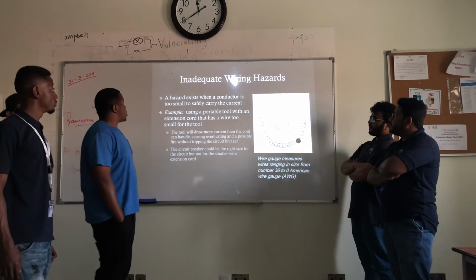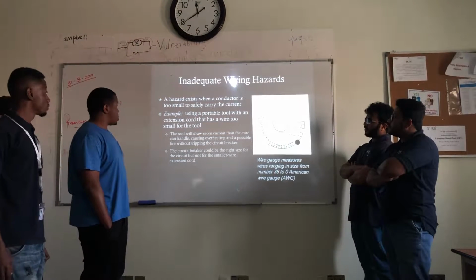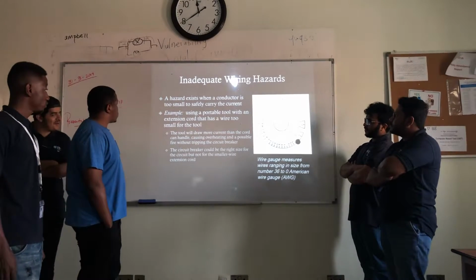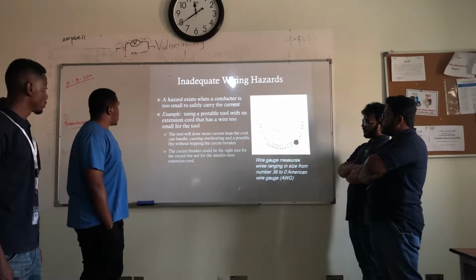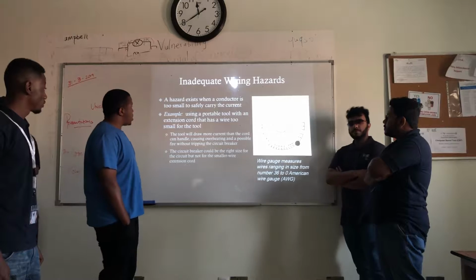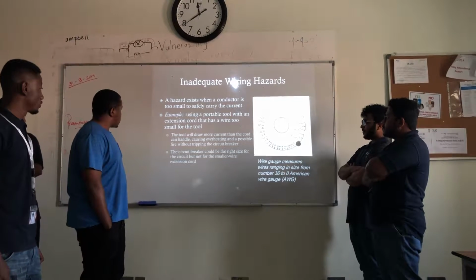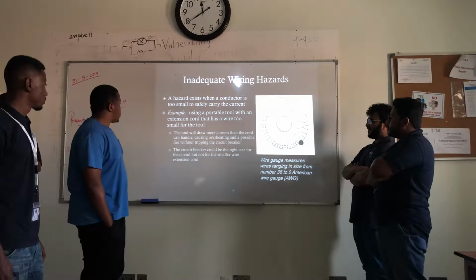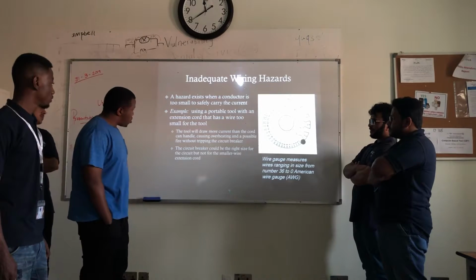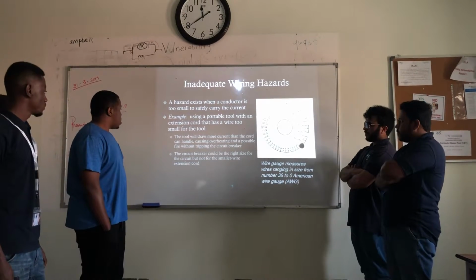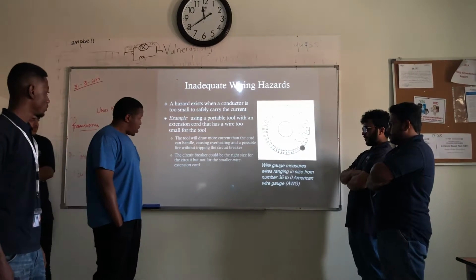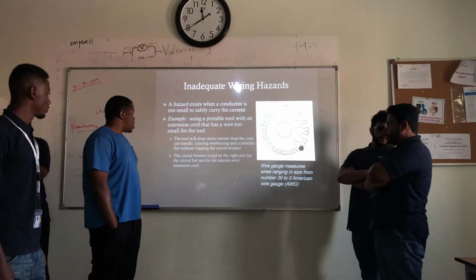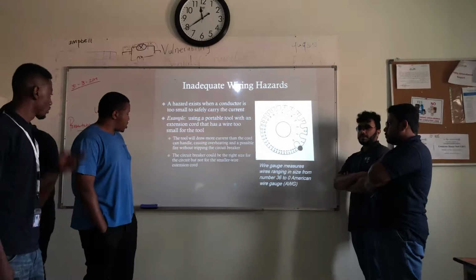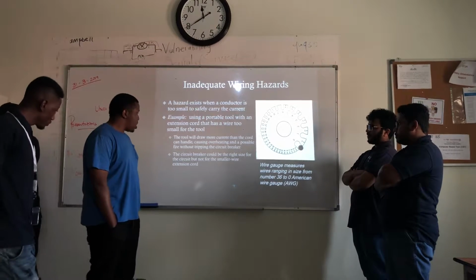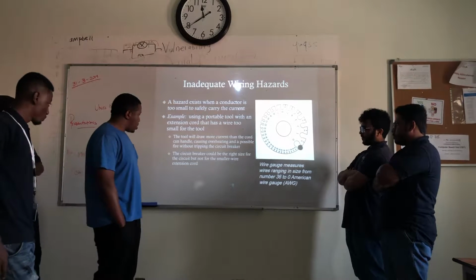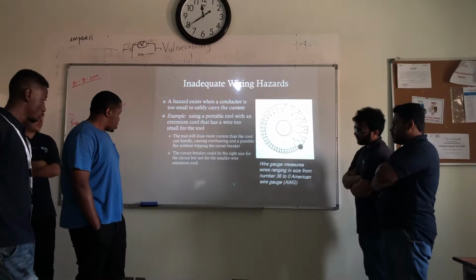In the inadequate wiring hazards, a hazard exists when a conductor is too small to safely carry the current. Example: using a portable tool with an extension cord that has a wire too small for the tool. The tool will draw more current than the cord can handle, causing overheating and possible fire without tripping the circuit breaker. The circuit breaker could be the right size for the circuit, but not for the smaller wire extension cord.